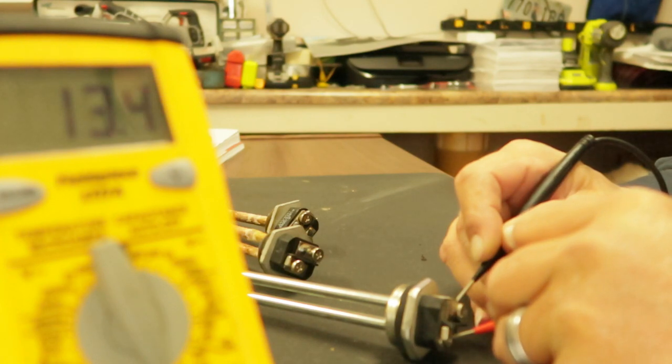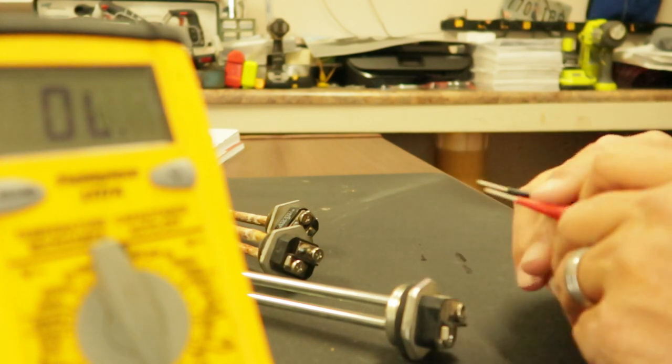And we'll get our 13.5 to 14 ohms. That is a good element. And that's how you would test it.